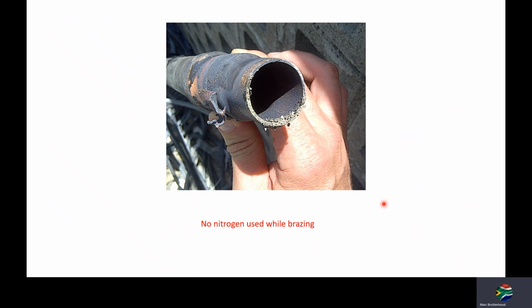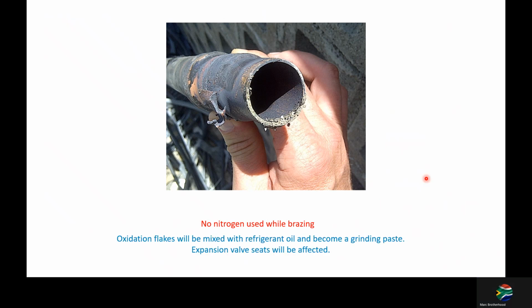Here we can see further where no nitrogen was used when brazing. So oxidization flakes will also now mix with the refrigerant oil and become a grinding paste. Besides damaging your bearings and your compressors, they will also cause expansion valve seats to be affected. On an electronic expansion valve, your valves aren't going to seat nicely on the chamfer, and you're going to get liquid refrigerant leaking through, and that's not what you want.